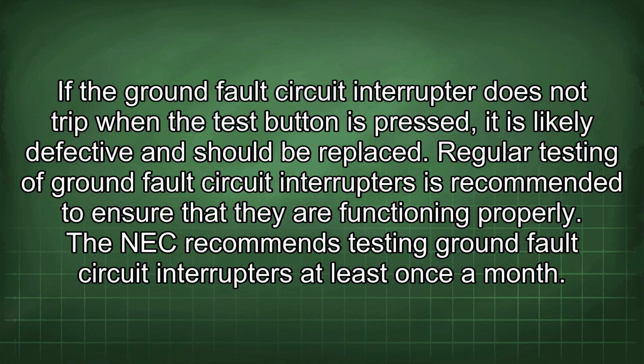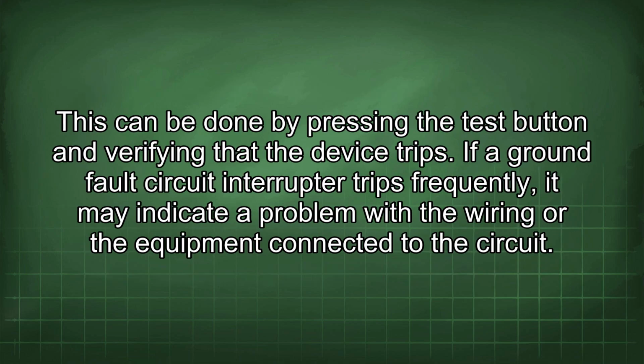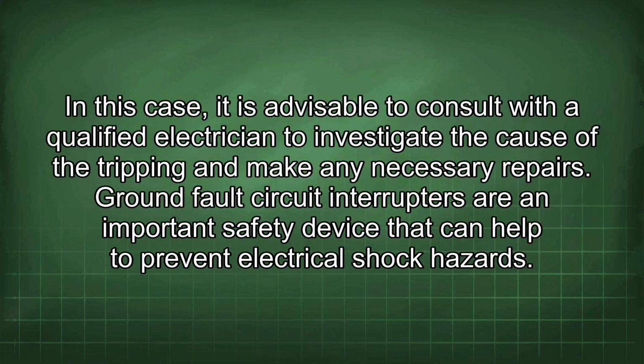Regular testing of ground fault circuit interrupters is recommended to ensure that they are functioning properly. The NEC recommends testing ground fault circuit interrupters at least once a month. This can be done by pressing the test button and verifying that the device trips. If a ground fault circuit interrupter trips frequently, it may indicate a problem with the wiring or the equipment connected to the circuit. In this case, it is advisable to consult with a qualified electrician to investigate the cause of the tripping and make any necessary repairs.